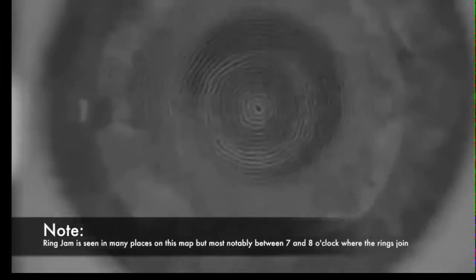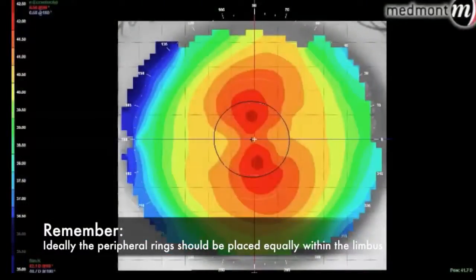However, in the second example, we see the mires are not intact and the Placido disk image shows ring jam. Both of these captures showed an accuracy in the top right-hand corner of 99%, yet the former will yield better quality data. Once we have achieved an ideal capture, we need to alter the colour scale to best match the data.